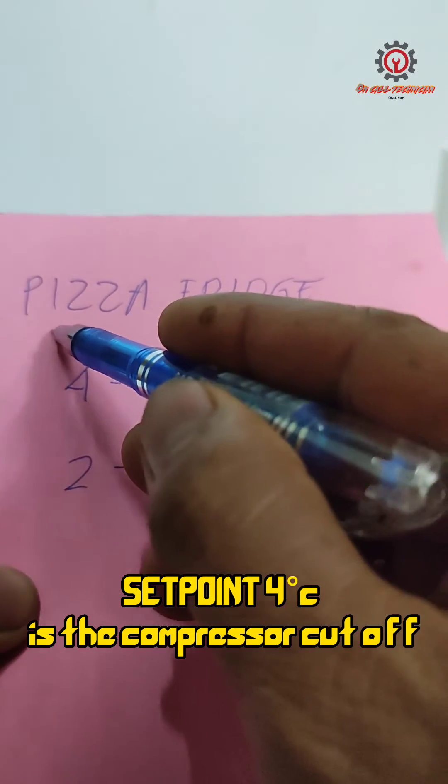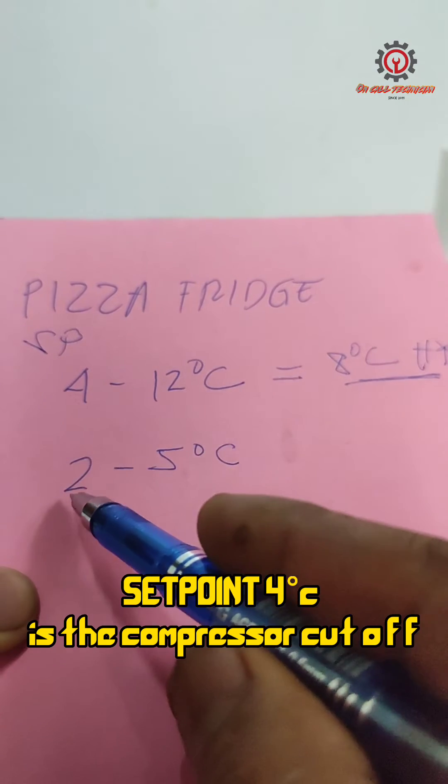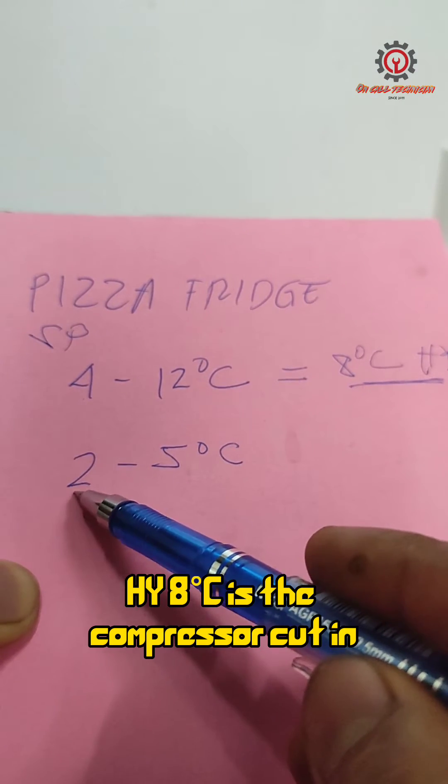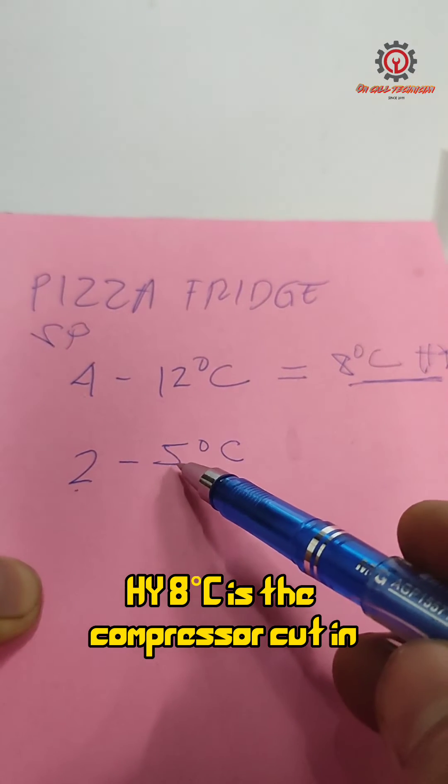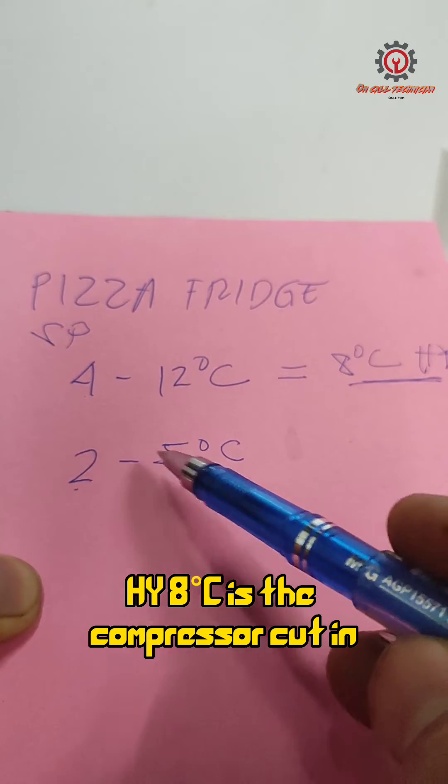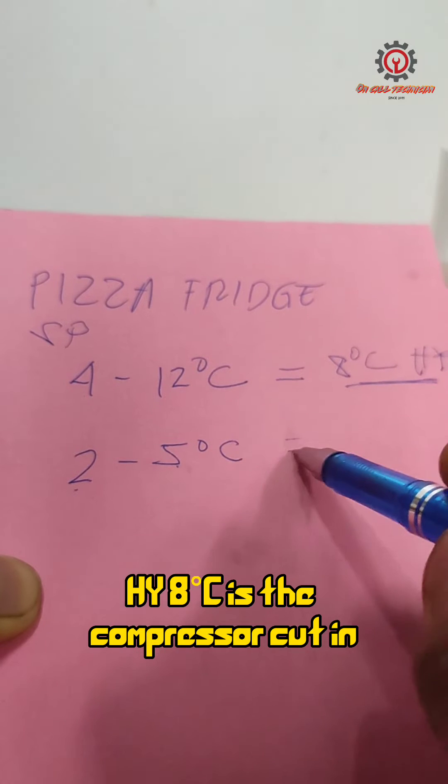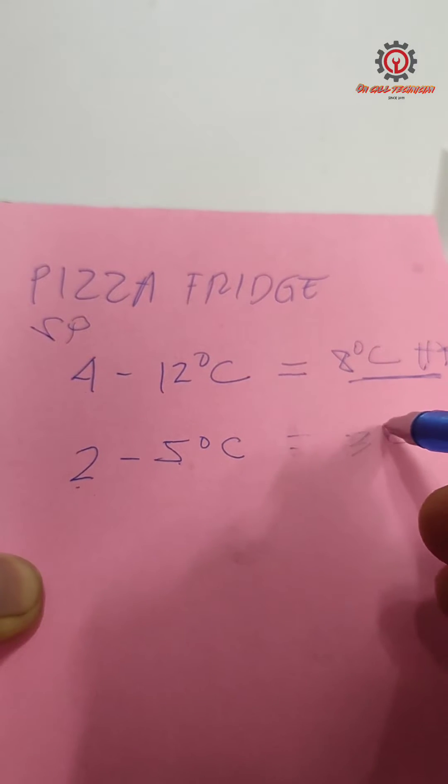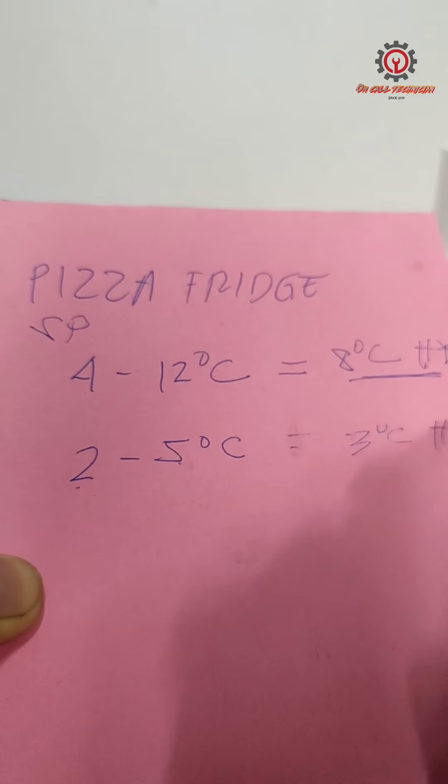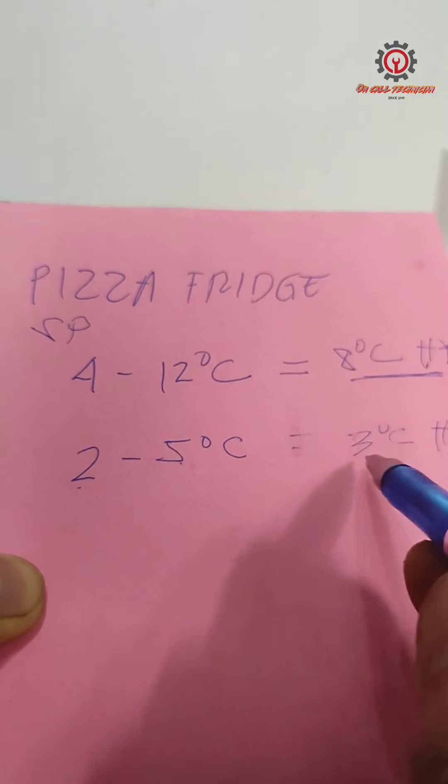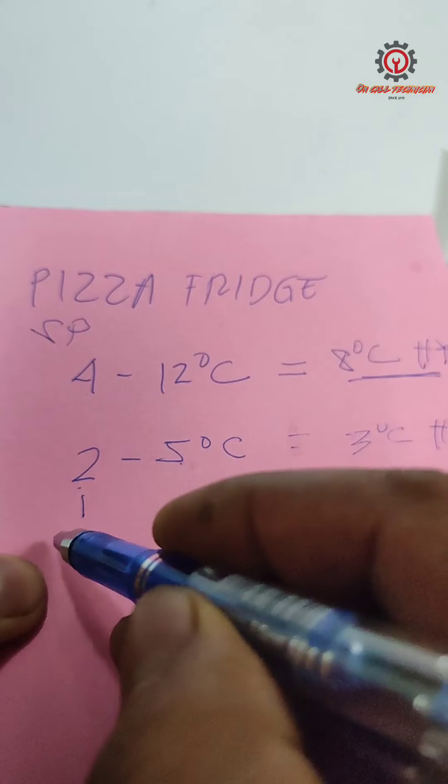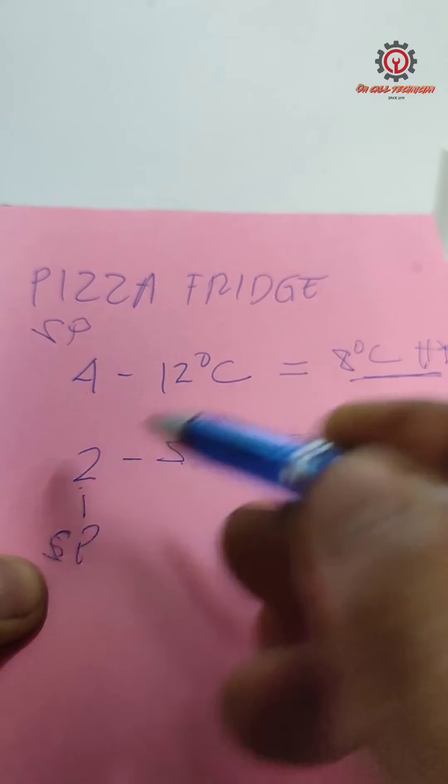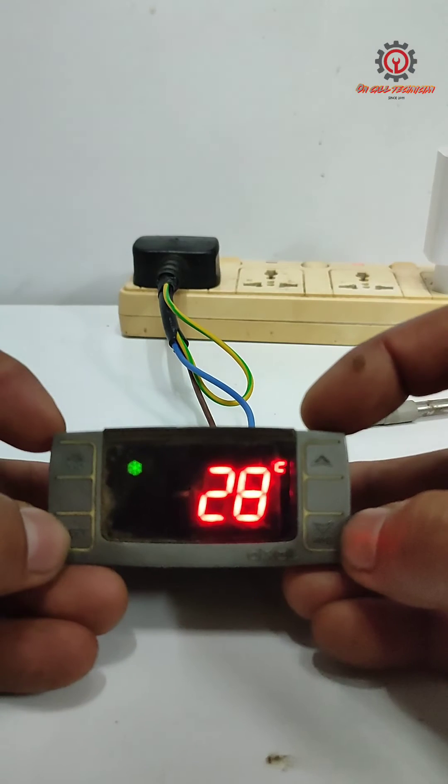The 4 here is the setpoint. So he wanted it to be 2 to 5 degrees Celsius. Now going to minus this: 5 minus 2 is 3 degrees Celsius. So this will be our HY, the differential, and this will be our setpoint. Now we're going to actually do the setup here.